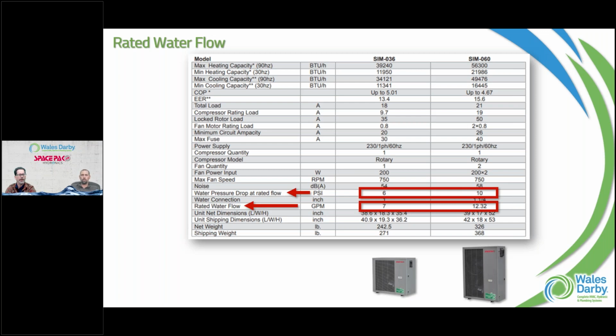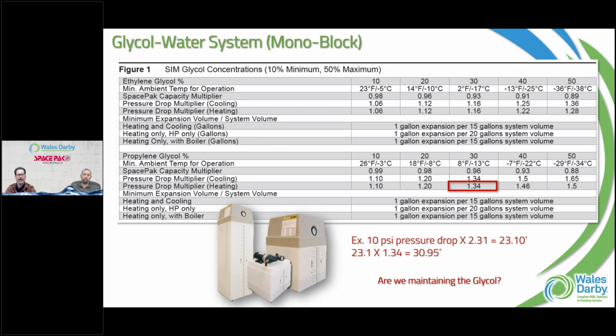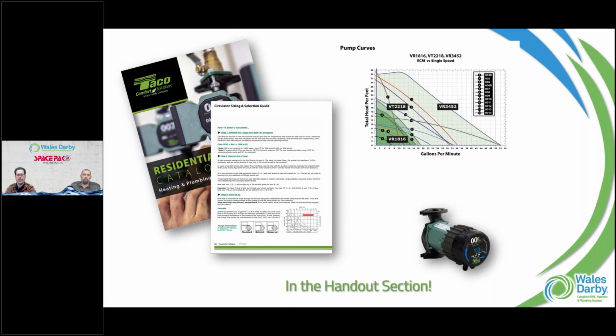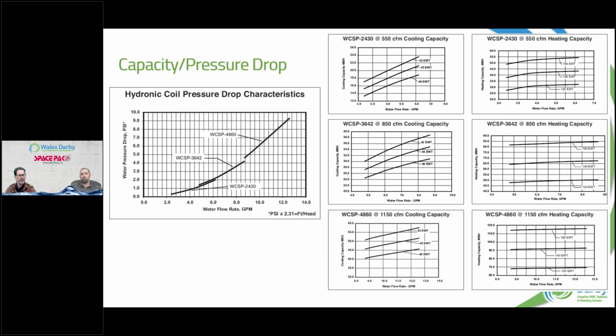I know we have some good people on the website, and I was looking up this morning about AHRI 550/590. That's actually what air to water heat pumps are being tested at. I just wanted to confirm. I know the air source stuff and what the parameters are there, and it doesn't seem to be reality for most of my applications, so I make people aware. You're reading specifications or outputs, but what were the test parameters really set at? It's kind of an eye opener when you hear some of those numbers. So for air to water, I've got to do a little more research. If someone has that information and wants to share it, that'd be awesome. What are the test parameters for air to water heat pumps for heating and for cooling?